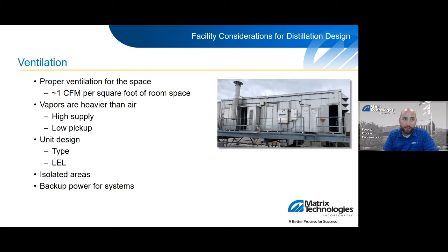For example, like a filler, you're going to have constant open product there. You may want to put spot exhaust fans in that location to make sure that you're not trapping any vapors anywhere. And it's also important to make sure that you have the system tied to a backup power supply. In the event of a power failure, that's the last thing you want to go, your ventilation system, and now you're just trapping all of that alcohol vapor, which is low, in the space, which could cause an event. So just make sure that you protect yourselves and hook that up, at least minimally exhaust, to a backup generator.